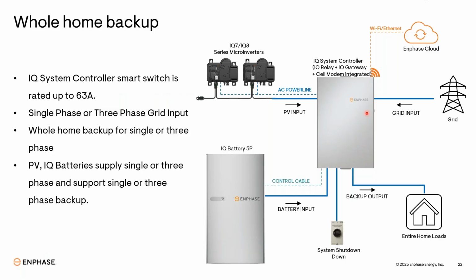You can provide either single phase or three phase grid input, and you can back up your complete home, either three phase or single phase. Your PV, batteries and supply will all be wired in a single phase configuration, and if you want three phase, you will wire all your connections as three phase only. And you will only take a backup output from the controller, because you are going to back up your complete house.